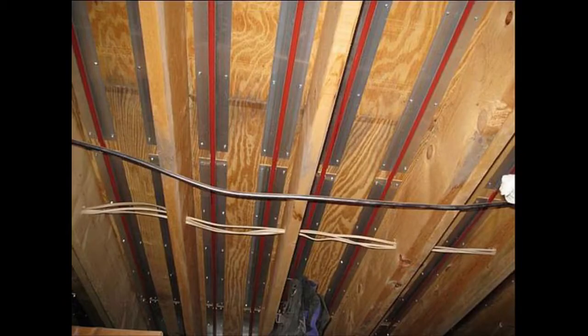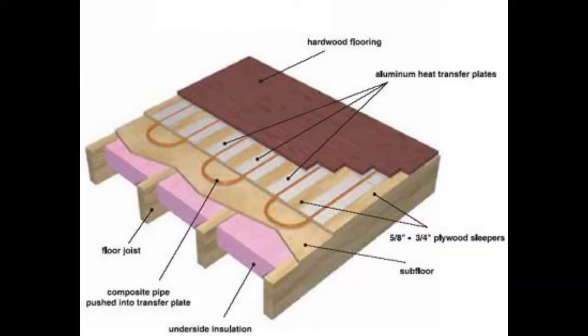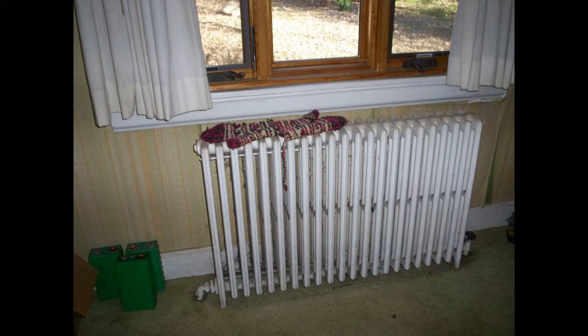Now you might ask, if I wanted radiant heat, why not go with underfloor radiant, which often uses water temperatures of less than 100 degrees? Well, it turns out that with the thick wood floors in my house, the required water temperatures would be about the same as with radiators, and of course it would cost thousands of dollars more to install. I'd also have to worry about overheating and warping the floor, whereas radiators are basically indestructible.